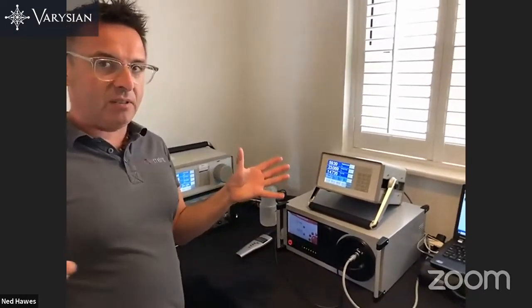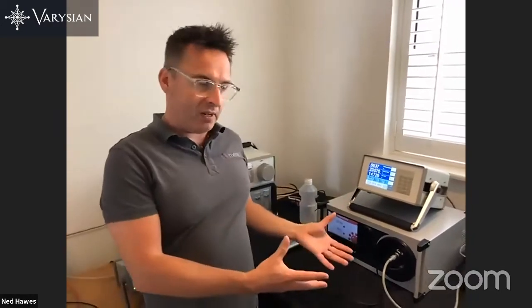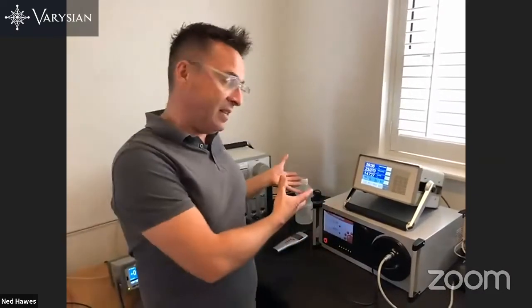The key thing to note is that when you're calibrating a humidity probe, which is a temperature and humidity probe, you need to generate a value, and you need to then take your instrument under test and compare it to a reference value. And what Patrick was talking about is the reference value that we advocate is the MBW. It works by measuring a dew point and the temperature and then calculating a relative humidity. It's obviously much more accurate than your standard RH probe, which is why it's used as a reference and a transfer standard to take a calibrated value from.